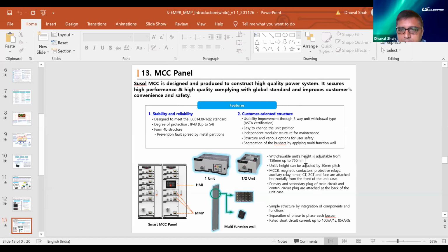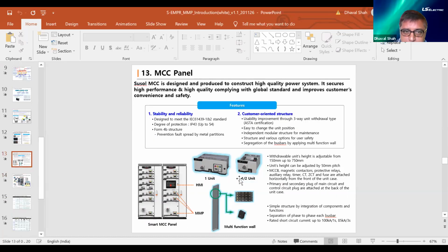Yeah, so you can see withdrawable units, height is adjustable from 150 mm to 750 mm, and MCCB and contactors have been horizontally mounted in each unit. So again, compactness is there. In fact, we have our own IEC 61439 solution with part 1 and part 2, which we can offer with IP43 as well as up to IP54 as the need-based solution, and all are ASTA certified. So we can offer the solution for IEC 61439 also.